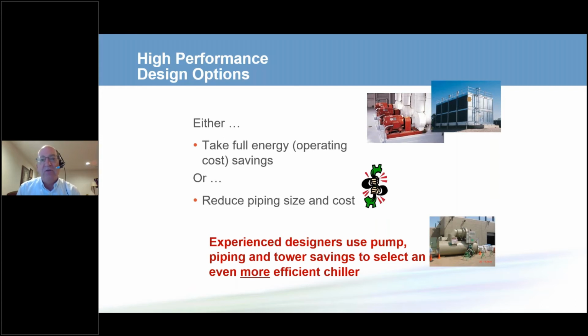Another option is to reduce the pipe sizes. When we reduce the pipe sizes, we reduce the costs, and particularly if there are long piping runs or it's a large chilled water system, those costs can be very large, and those savings can be very large. But we now have a decision to make. Do we keep the pipe sizes the same and save all the energy and energy costs? Or do we reduce the pipe sizes, reduce the first cost more, but not save as much energy? And that's always a decision that can be made by the project team for the specific application.